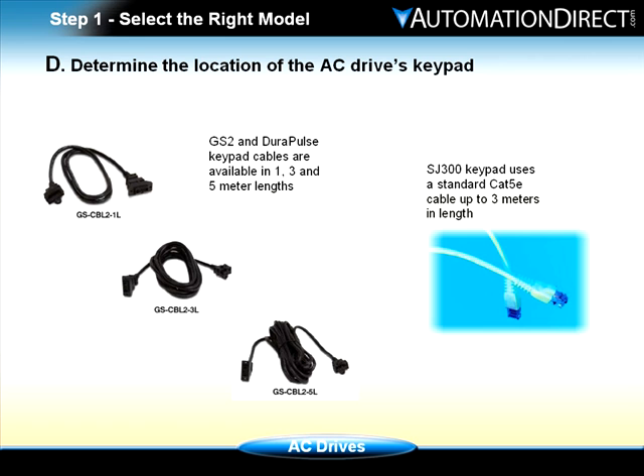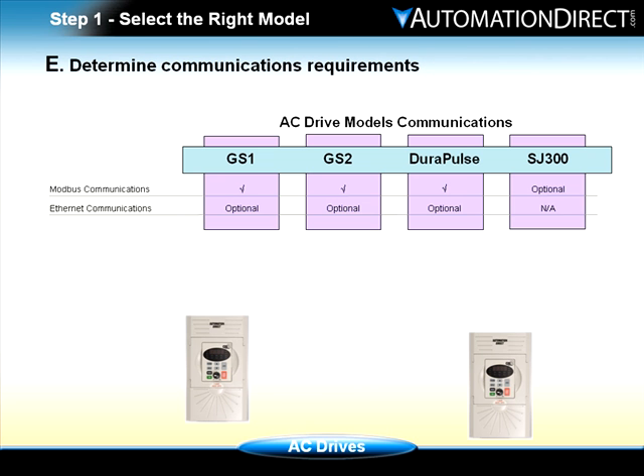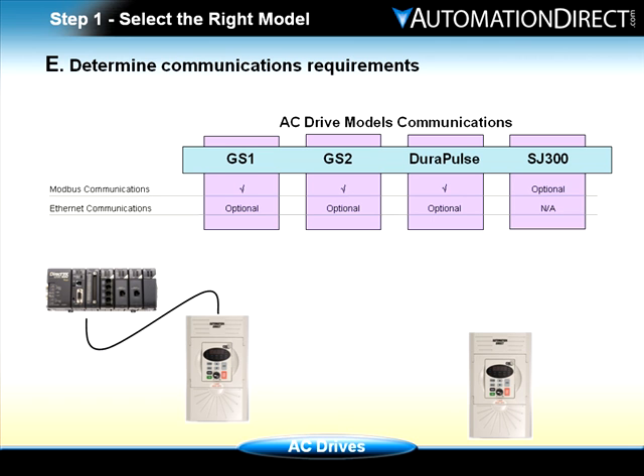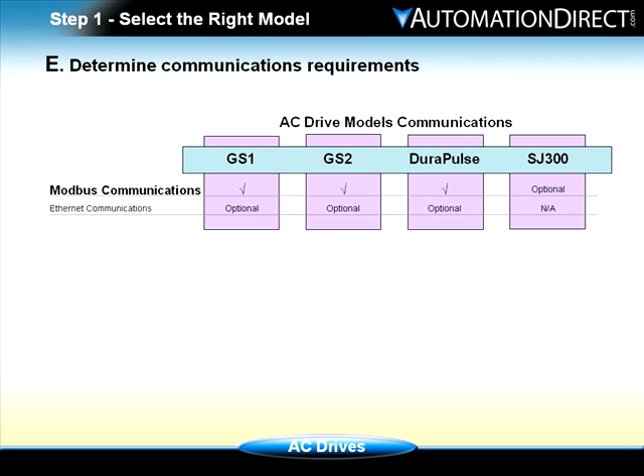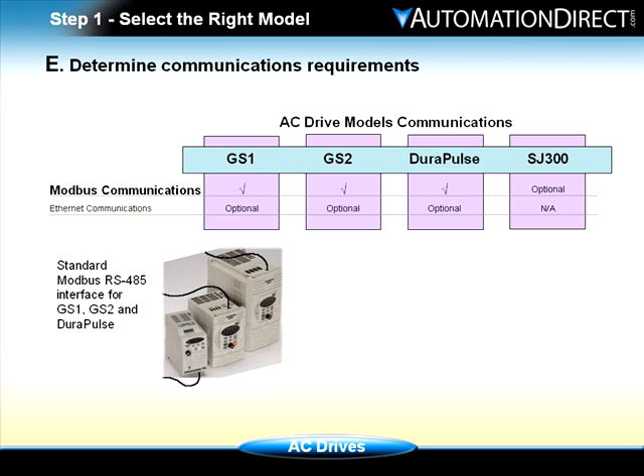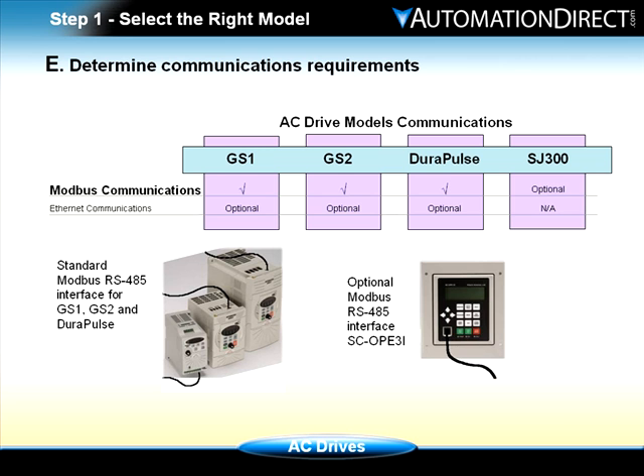A standard UTP Category 5 Ethernet cable up to three meters in length can be used for the SJ300 keypad. A serial communications interface can be used to connect the AC drive to other devices that function as a master. The master device can control the AC drive with the serial interface instead of using digital and analog I/O, and can also monitor status of various AC drive parameters such as speed, current, and fault status. The GS1, GS2, and DuraPulse AC drives have a standard Modbus RS-485 serial interface. The SJ300 requires an optional SC-OPE-3i with a built-in serial communications interface.